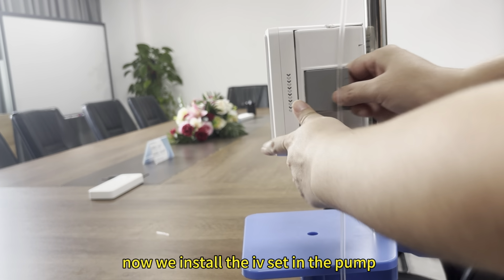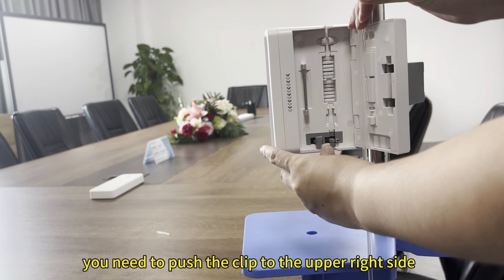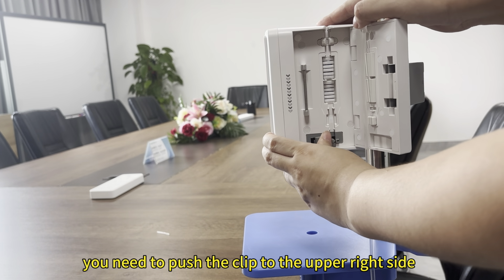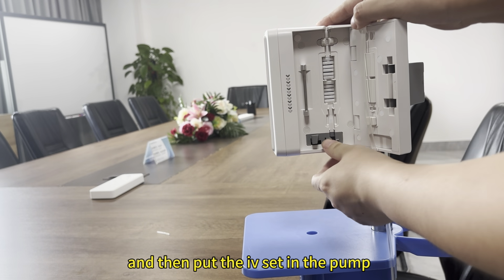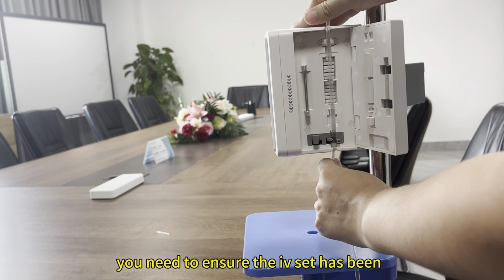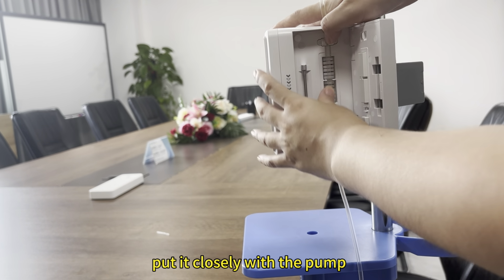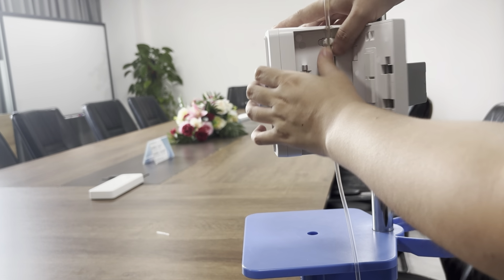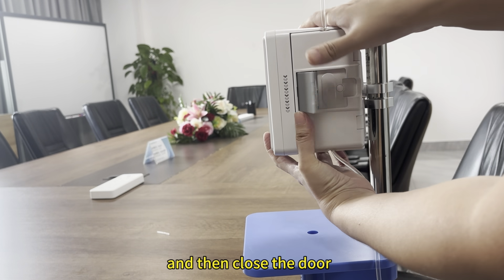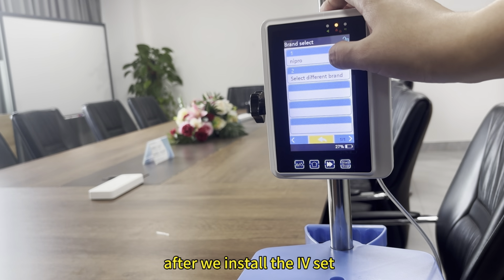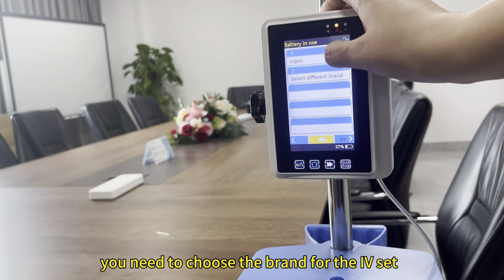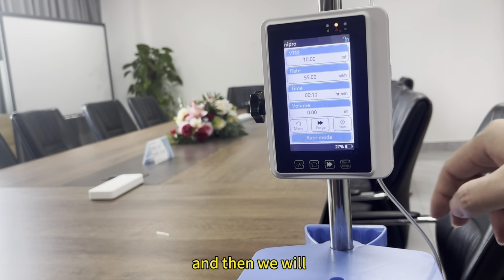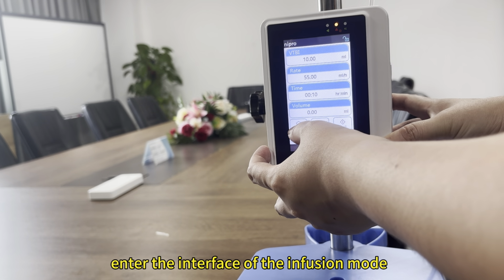Now we install the IV set in the pump. You need to push the clip to the upper right side, and then put the IV set in the pump. You need to ensure the IV set has been put closely against the pump, and then close the door. After we install the IV set, you need to choose the brand for the IV set, and then we will enter the interface of the infusion mode.